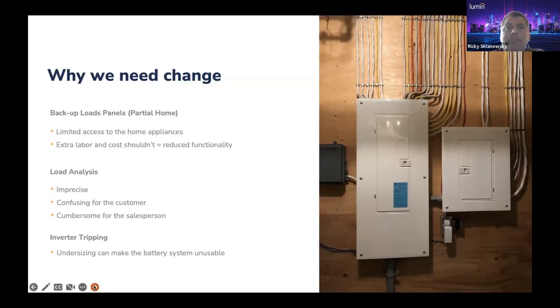If you imagine a traditional backup system with a few loads in the protected loads panel, say a customer wants to self-consume, which we'll see more of in places like California with NEM 3.0, only those few loads in the protected panel will have access to the PV and battery generation, while the majority of loads remain in the main service consuming utility-generated power. By installing Lumin in the main service panel, there's no need for the customer to spend extra money and labor on a separate load center.